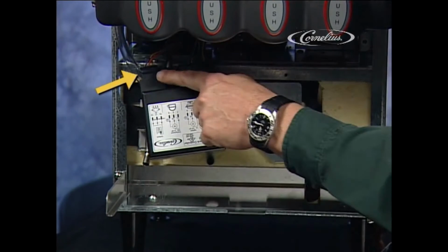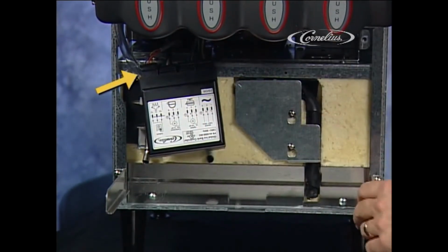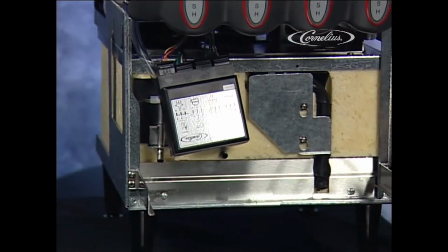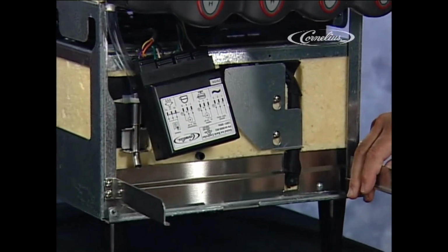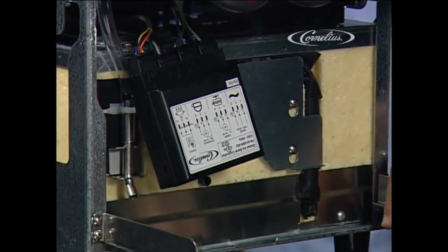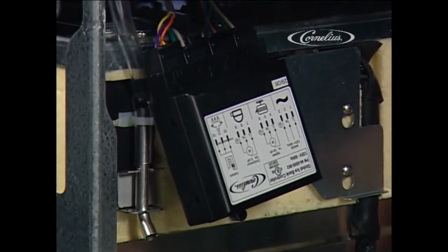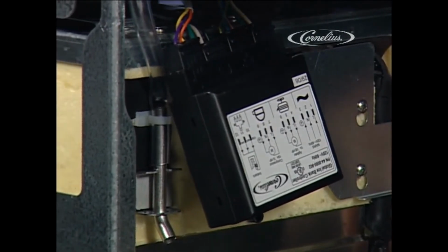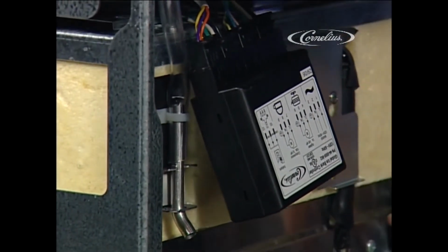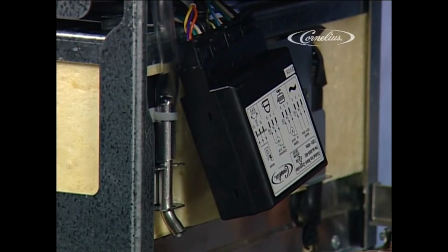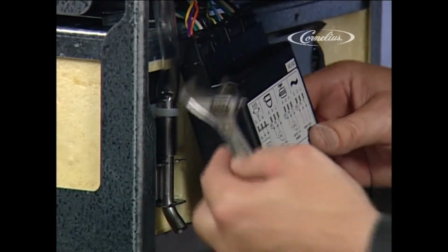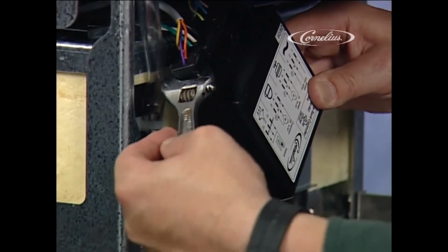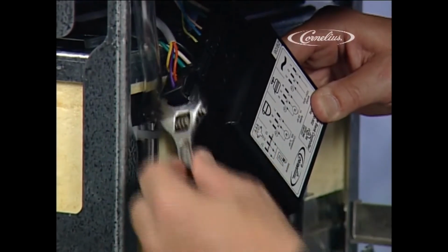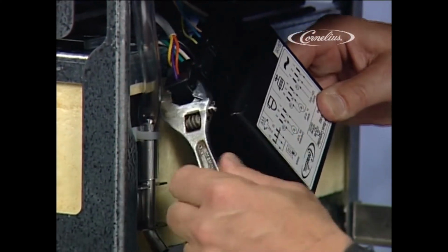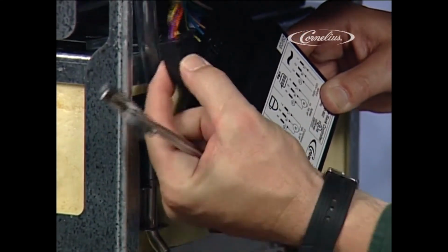Next, we need to remove the probe connector, which is the one on the far left side of the box and is marked with a picture diagram. These connectors are very tight. Using any kind of pliers or gripping device will crack and break the connector cover. The best method to remove this is to use either an adjustable crescent wrench or a 7/16 open-end wrench. Slide the wrench across the connector and gently rock up and down. This will loosen and raise the connector out of the IBC so it can be easily removed.